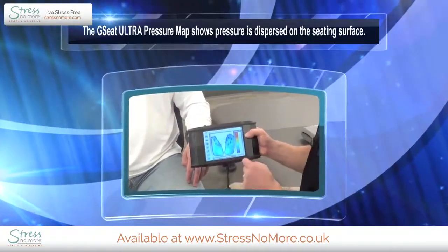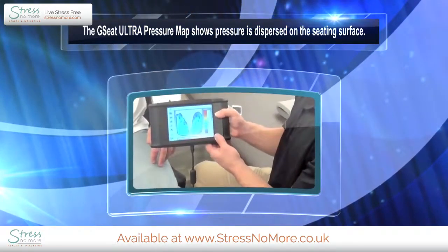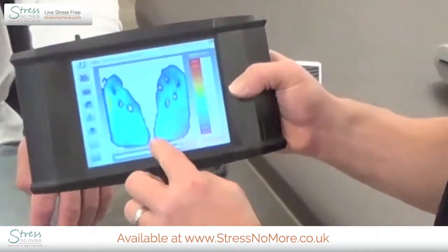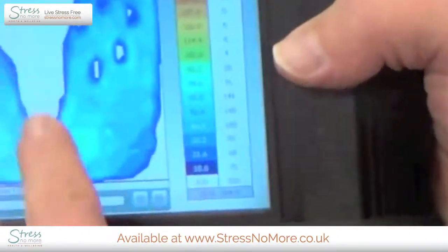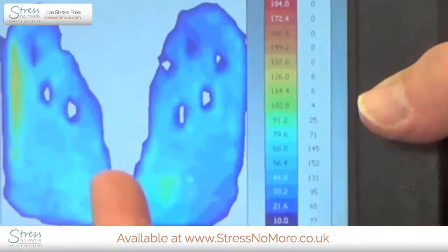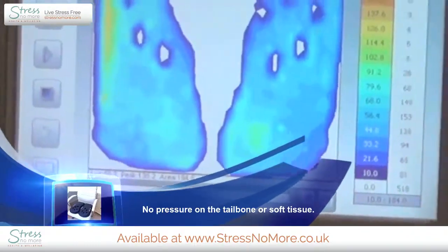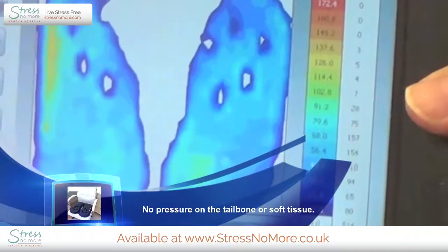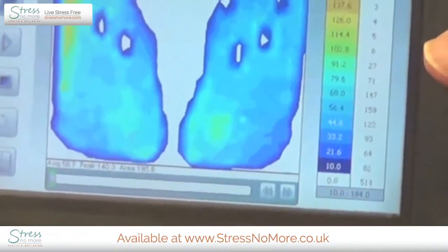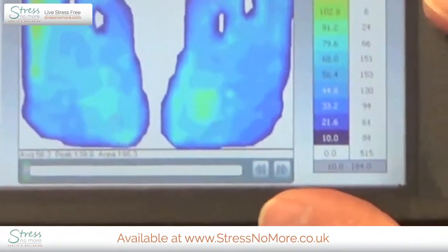As you can see here by the image, Dan's going to explain what those colors mean, but it looks like things are going pretty good for the GSeat. With comfort and pressure relief, what we look at is the white and blue are little to no pressure, up to the red is high pressure to the point where we'd be worried about a pressure sore. You can see that in the middle here where the cushion offloads the buttocks, there's no pressure on the tailbone or middle of the buttocks, and out here on the edges are low blue pressures that are exactly what we'd want to see, even if a person had a risk for skin issues on their bottom. And that's a great pressure mapping for pressure relief right there.